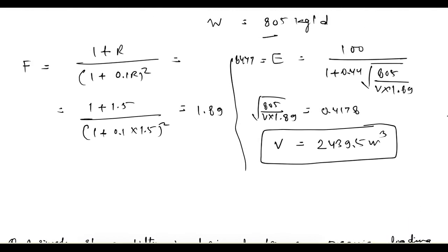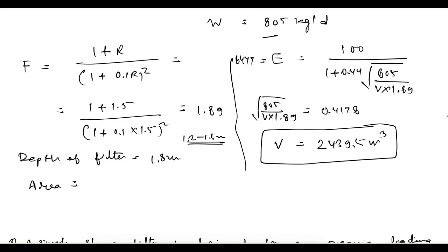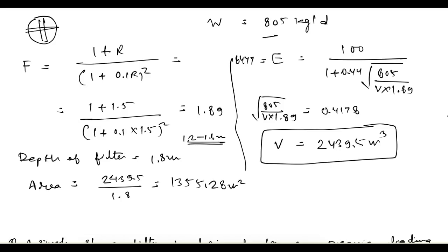Since depth is not given, we assume depth of filter. For a high rate filter the range is 1.2 to 1.8 meters; let's take 1.8 m. Area = 2439.5 / 1.8 = 1355.28 m². For a circular filter, using π/4 × d² = 1355.28, the diameter works out to 41.5 meters.